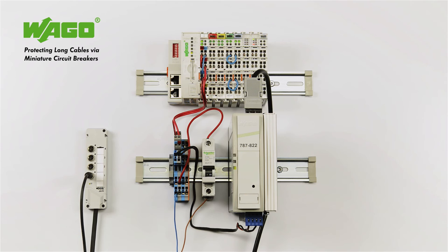In this setup, we have connected a 15-meter cable to the sensor actuator box. A sensor is connected to the box by an additional 3-meter cable. Now we are simulating a short circuit in the sensor. Although the overload LED is lit on the power supply, the miniature circuit breaker fails to trip. In this case, the best possible outcome would be the thermal section of the fuse responding after an undefined period of time.